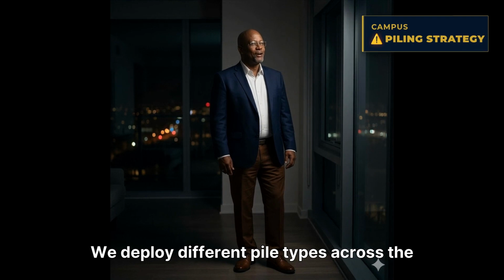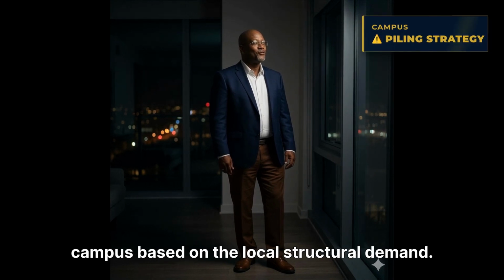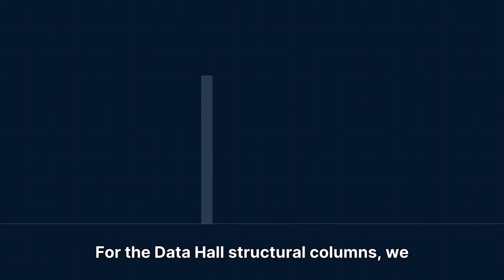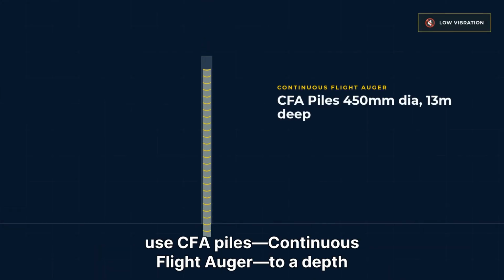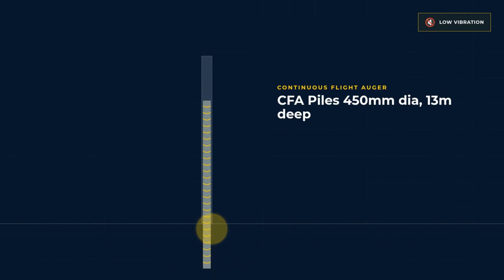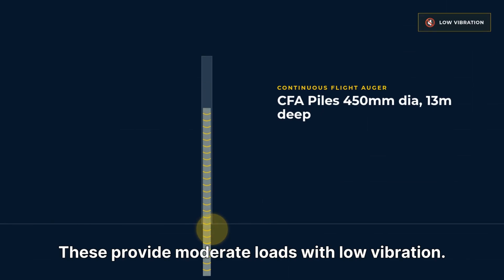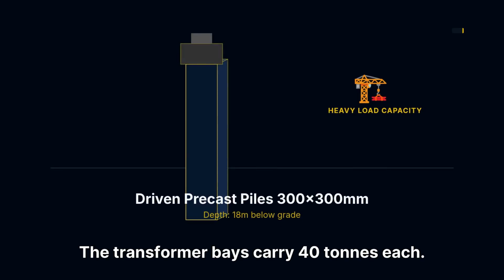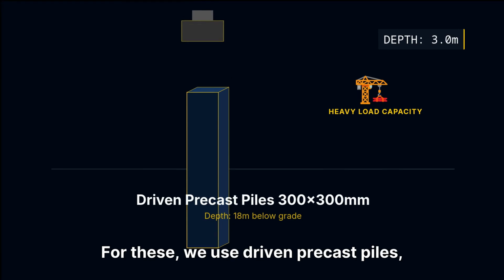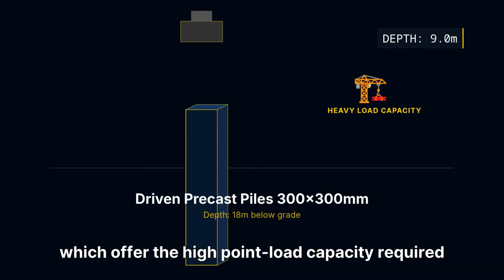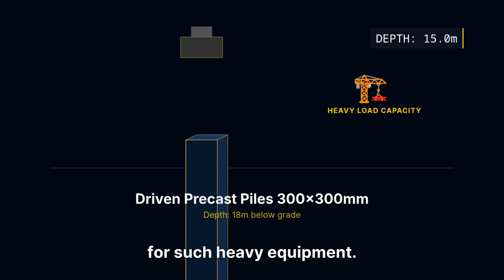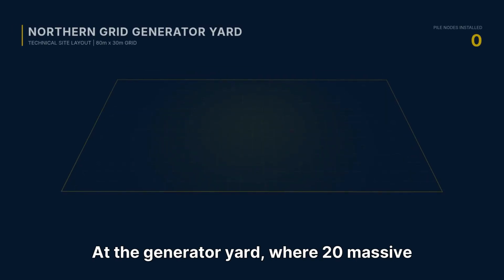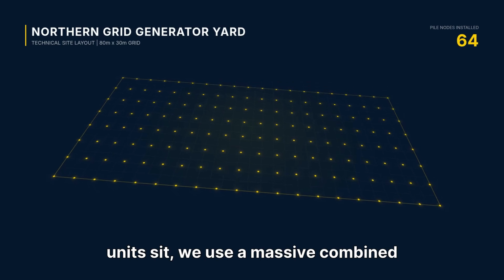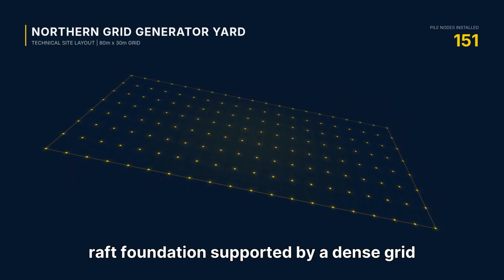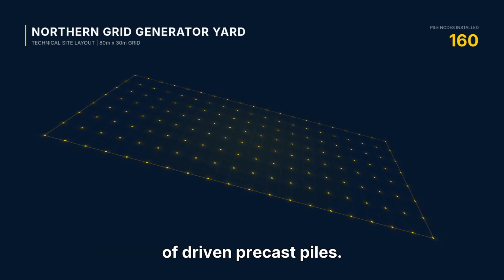We deployed different pile types across the campus based on the local structural demand. For the data hall structural columns, we use CFA piles, continuous flight auger, to a depth of 13 meters. These provide moderate loads with low vibration. The transformer bays carry 40 tons each. For these, we use driven precast piles, which offer the high point load capacity required for such heavy equipment. At the generator yard, where 20 massive units sit, we use a massive combined raft foundation supported by a dense grid of driven precast piles.